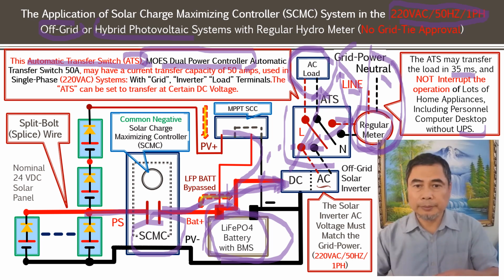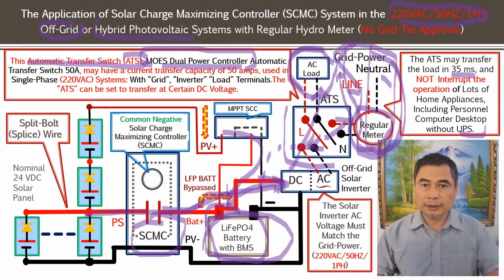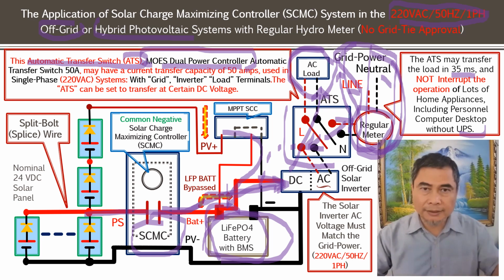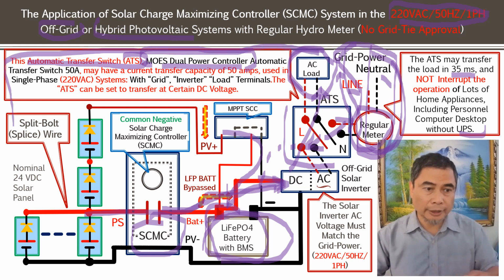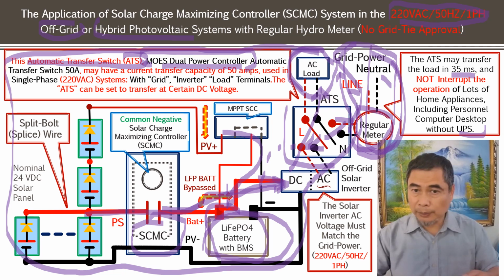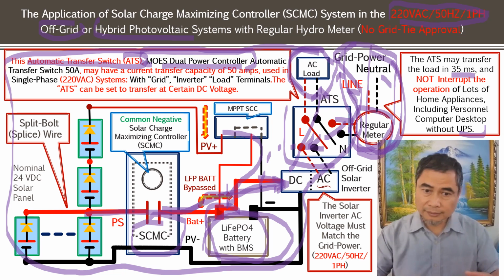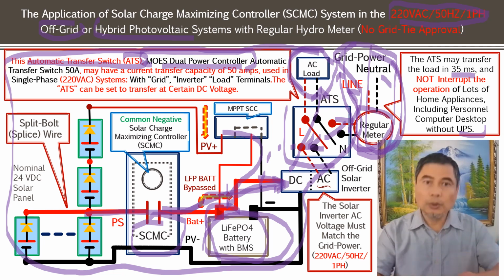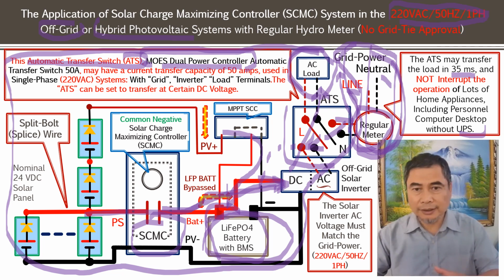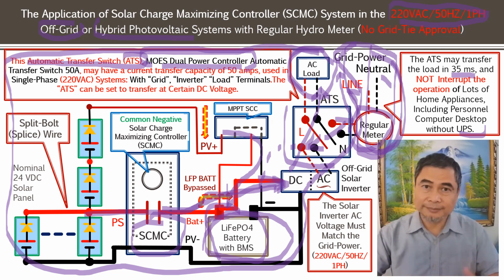And the other benefit is when the power grid is down, whatever the scenario, like a tropical storm or whatever happened, and nobody has grid power, you could still have the power from your solar array system to power the emergency load. And if you size the battery bank big enough, you can also make sure this system will carry the load during off-peak hours as well, at night. So this is the benefit and the application.